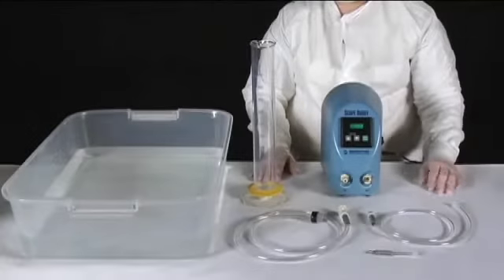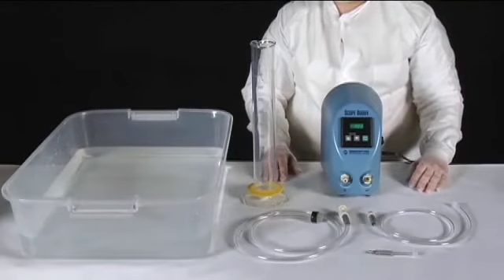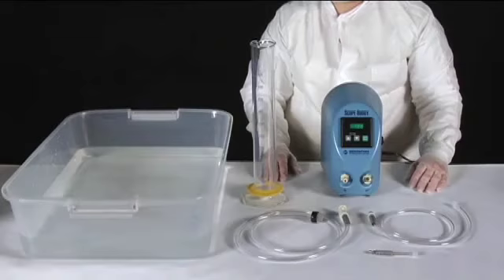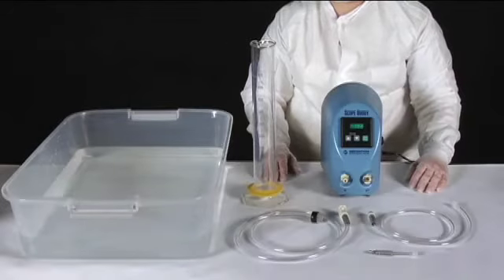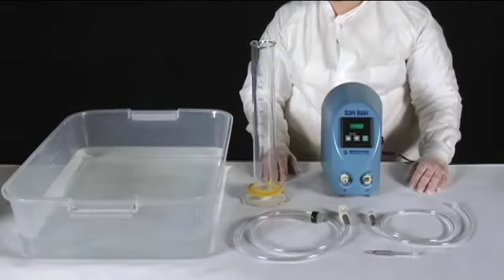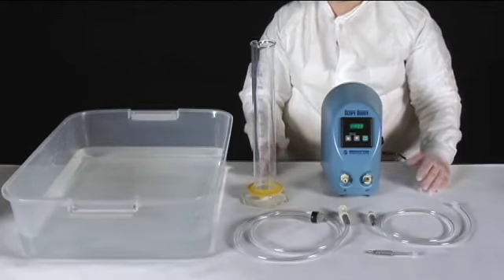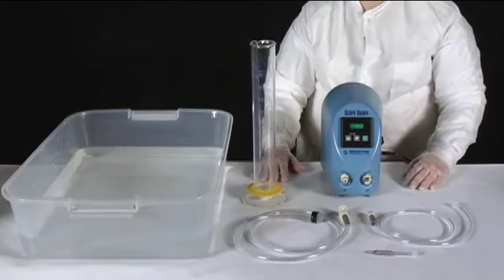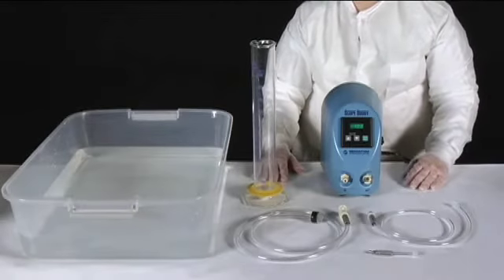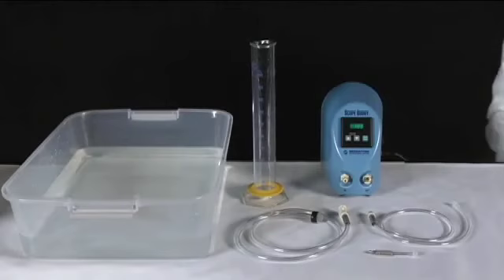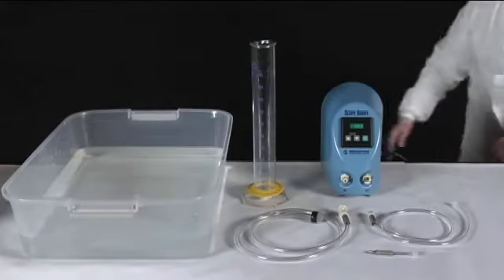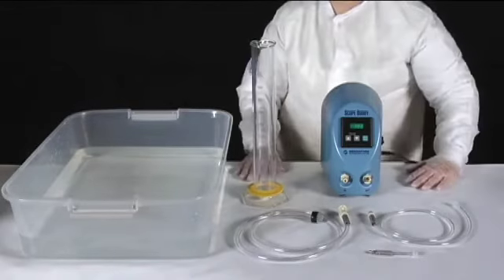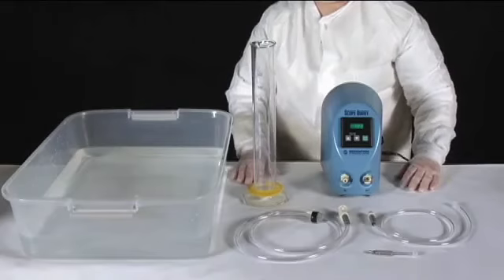To verify the Scope Buddy device is operating properly and delivering the correct amount of fluid, a flow validation test should be conducted daily. This validation test is easy to perform and quickly determines if the device is delivering the correct amount of fluid. It is important that a quality assurance test is done and documented each day before using Scope Buddy on an endoscope. Performing the Scope Buddy flow validation test.